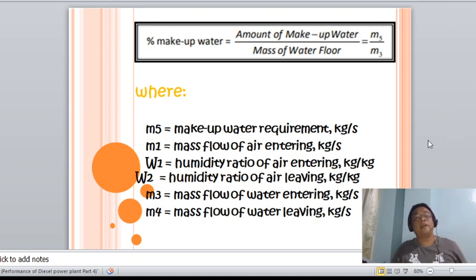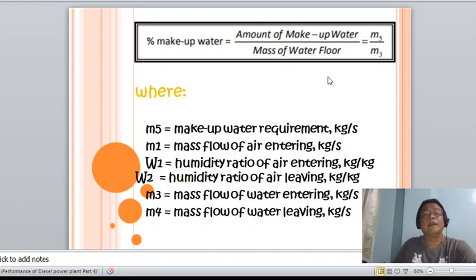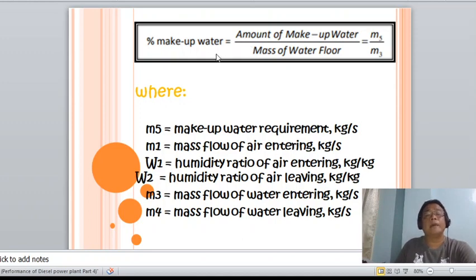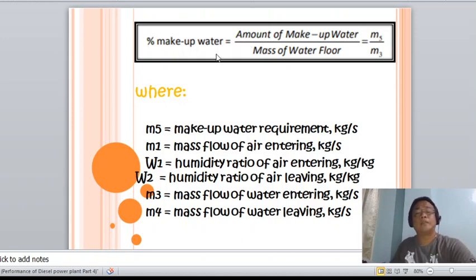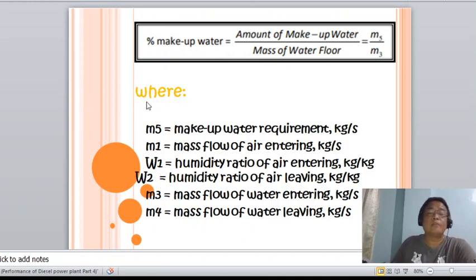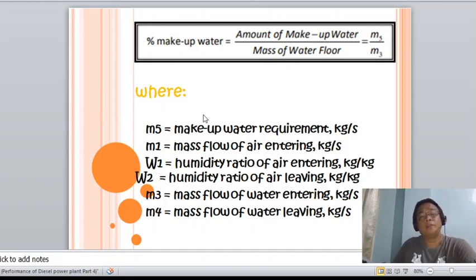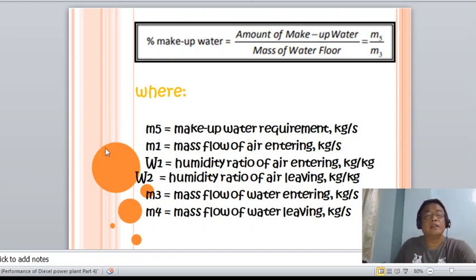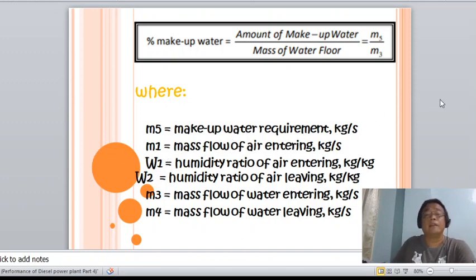The percent makeup water equals the amount of makeup water divided by the mass of water entering. Where m5 represents the makeup water requirements in kilograms per second, m1 is the mass flow of air entering the tower, w1 is the humidity ratio of air entering, w2 is the humidity ratio of air leaving, m3 is the mass of water entering, and m4 is the mass flow of water leaving the tower.